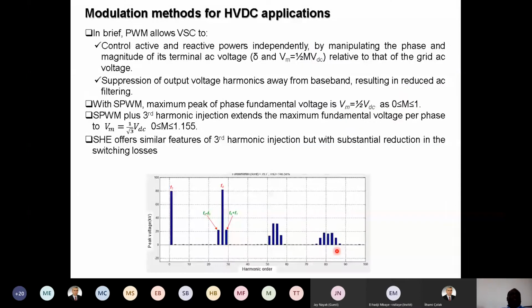And modulation methods for HVDC. In brief, the modulation allows the VSC to control active and reactive power independently, which, as I explained, is by manipulating the phase and magnitude of its terminal voltage relative to the grid voltage, which are these two quantities. So the independent control is not because of DQ, as people may mention in the papers, but because we have 2 degrees of freedom. This is why we can control the active and reactive power of the VSC independently. While in LCC, because we only control the firing angle, P and Q are coupled.